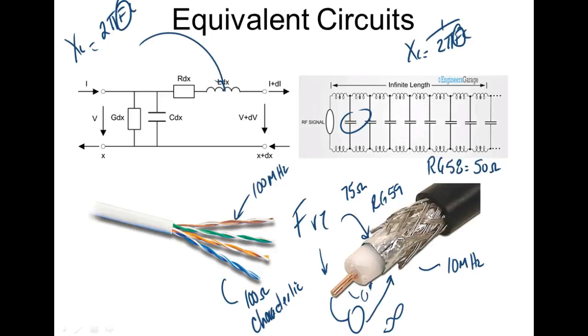That means when we splice or terminate these things, we really have to follow some guidelines to maintain the twist in the cable, to maintain the spacing between the two conductors. We've got to maintain that spacing. So with coax cable, we just can't splice it together. We have to come back and do that properly.